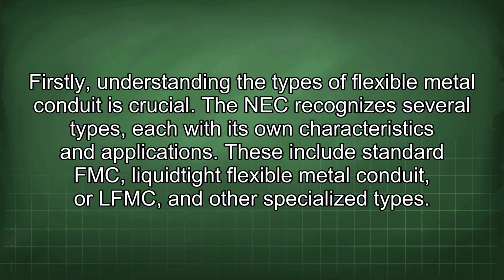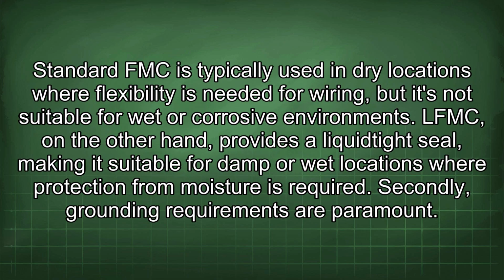Firstly, understanding the types of flexible metal conduit is crucial. The NEC recognizes several types, each with its own characteristics and applications. These include standard FMC, liquid-tight flexible metal conduit, or LFMC, and other specialized types. Standard FMC is typically used in dry locations where flexibility is needed for wiring, but it's not suitable for wet or corrosive environments. LFMC, on the other hand, provides a liquid-tight seal, making it suitable for damp or wet locations where protection from moisture is required.